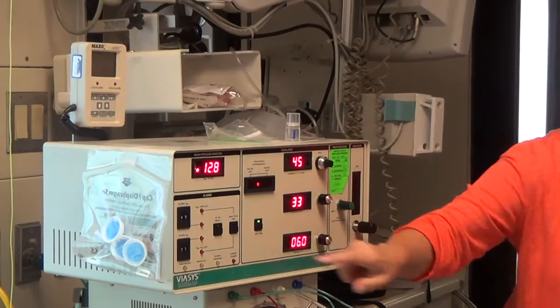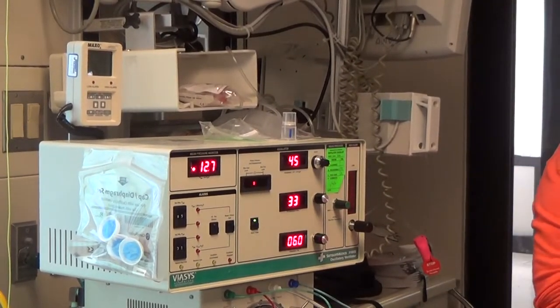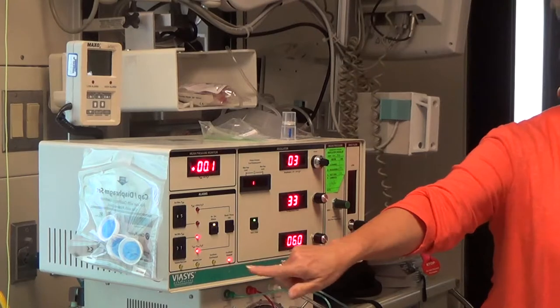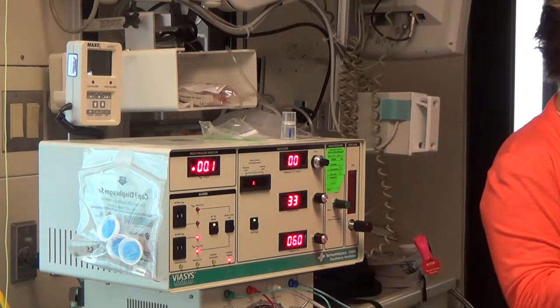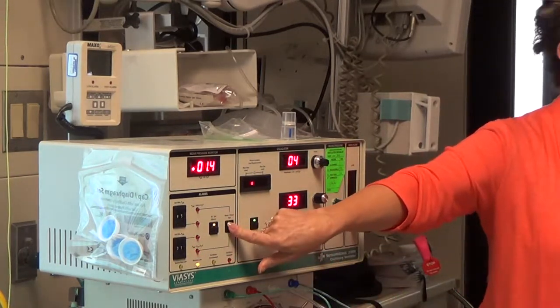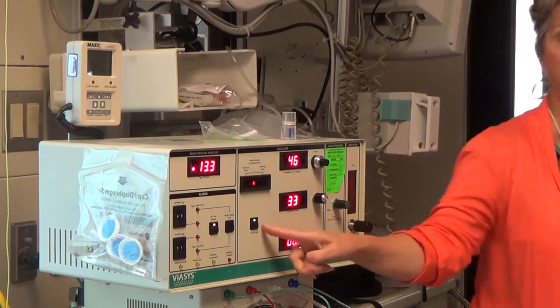Okay. So the next alarm is mean airway pressure less than 5 centimeters of water pressure. What will cause that? A leak in the airway. A leak, a disconnect, okay? All right, so piston stop. Again, all it's telling me is you gotta fix the problem and reset it, okay? See how it doesn't start? 1-1000, 2-1000.